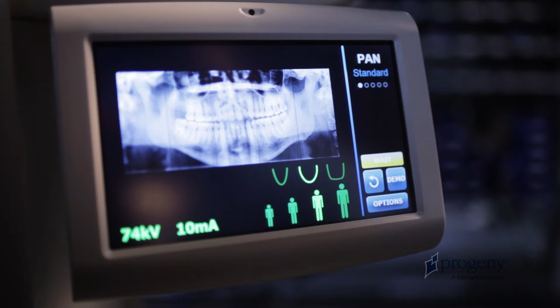A red Ready status indicates that the Vantage is in an unknown position. A yellow status indicates that the Vantage is in the entry position. A green status indicates that the Vantage is ready for imaging, and a blank status indicates that the Vantage is in the exit position. To reset the overhead support, tap the cycle button on the Vantage Touch once. Doing this brings the Vantage to the patient entry position.